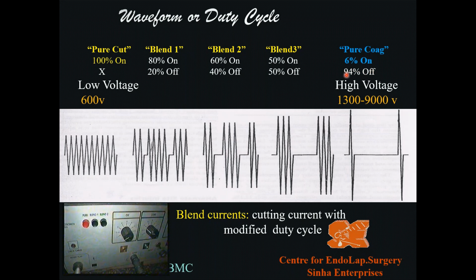So this is one of the machines, just to make you understand. So here basically you're looking at the blend mode. See, blend 1, blend 2, the cut and the coagulate. So when you increase this, you're increasing the voltage here. When you're increasing this, you're increasing the voltage out here. Okay. Now, what are the blend currents? The blend currents are in-between currents where from 100% on to 6% on, you have a range of on and off. In pure cut, what is it? Continuous. So on for 100% time. Until you press the pedal, it is on. Once you stop the pedal, it stops.